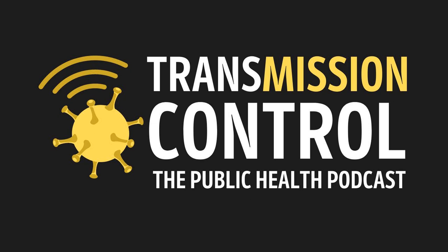They were not working. Why did the FDA not know that beforehand? When you put a device into the field and give it to hospitals to perform these minimally invasive endoscopic procedures, the manufacturer's responsibility is to sell the product. We get that. How did these devices get into the field where their instructions apparently had not been adequately validated for effectiveness - meaning if staff followed the actual cleaning and disinfection protocols detailed in the endoscope manufacturer's instructions for use, the data suggests the endoscope could remain contaminated with organisms? Why did the FDA not pick this up, detect this, and understand this years earlier?